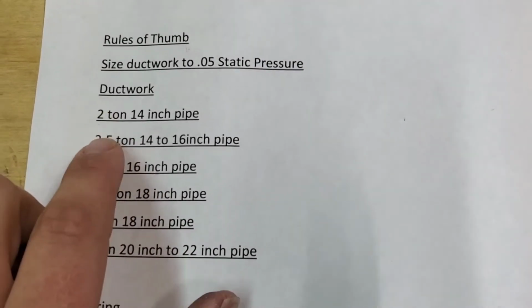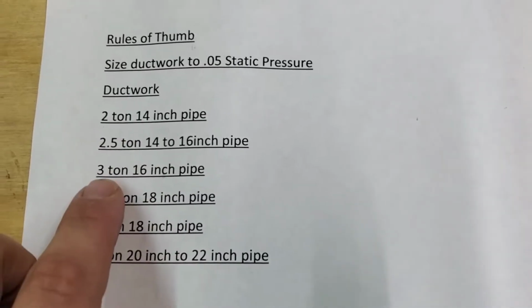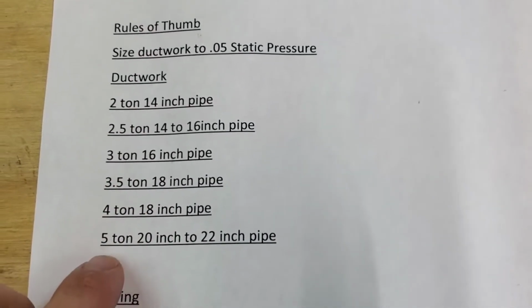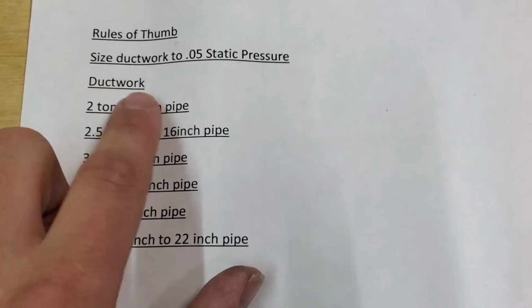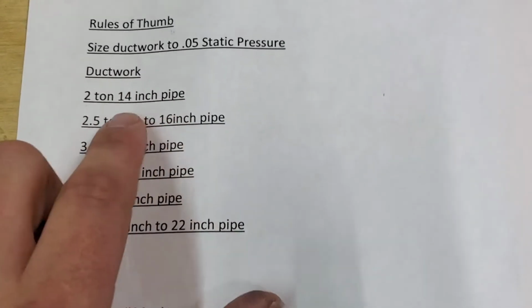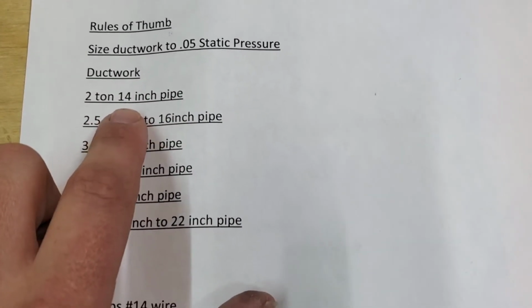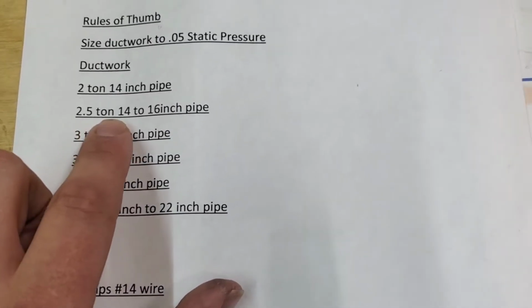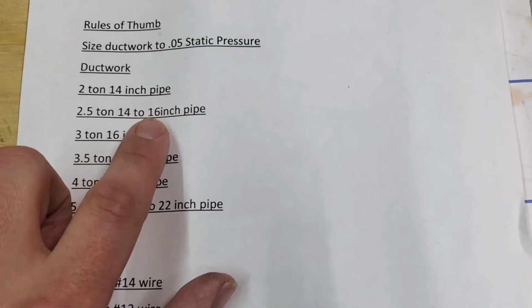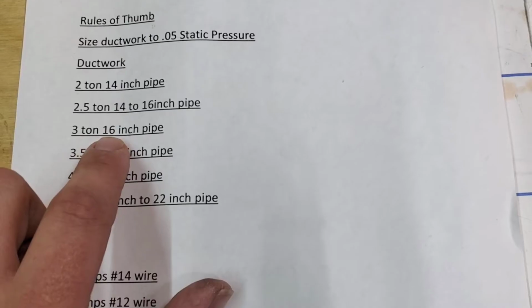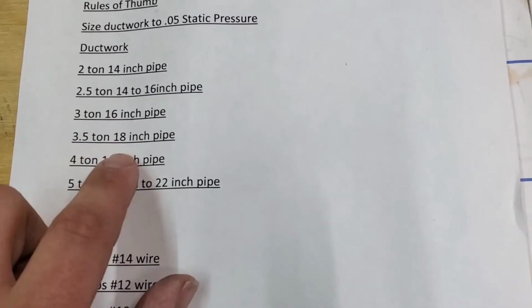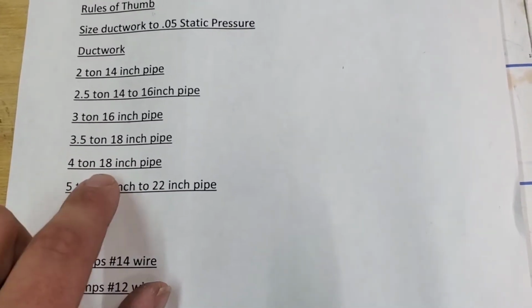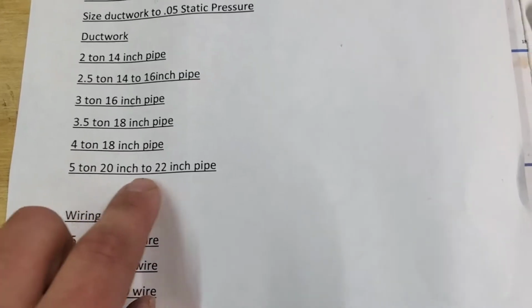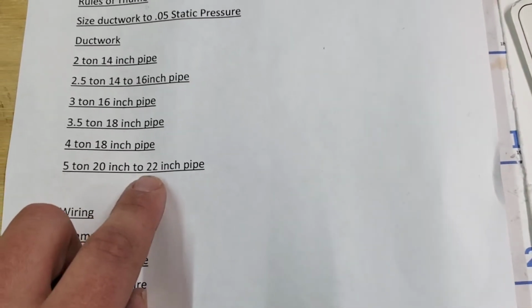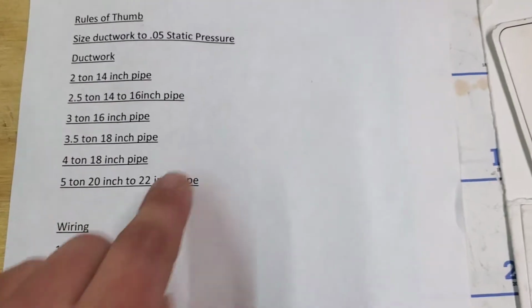So I've made a little sheet here, and I've got a tonnage for the equipment: 2 ton, 2.5 ton, 3 ton, 3.5 ton, 4 ton, 5 ton. And I've got a ductwork pipe size, okay? So 2 ton needs at least a 14-inch pipe. Your 2.5 ton needs a 14 to, honestly, it needs a 16-inch pipe. 3 ton needs at least a 16-inch pipe. 3.5 ton needs an 18-inch pipe. 4 ton, at least 18. And then 5 ton, I would stick with the 20 to 22-inch pipe. So this is what you need, all right?